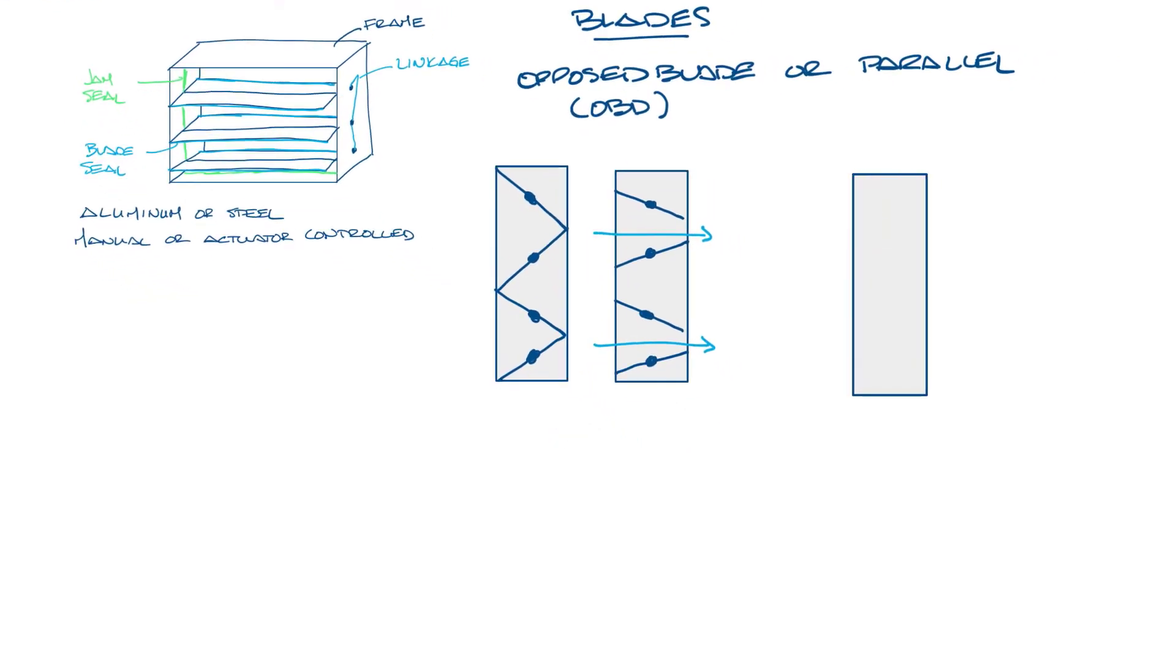Parallel blades work in parallel like this. You can see that as the damper closes the airflow will be directed towards the direction of the damper blades. Parallel blades typically require more torque to open but less to close compared to OBDs. The relationship between flow rate and position of the blades is not linear, meaning that 25% open may not be 25% flow or that opening another 5% will give you 5% more flow.